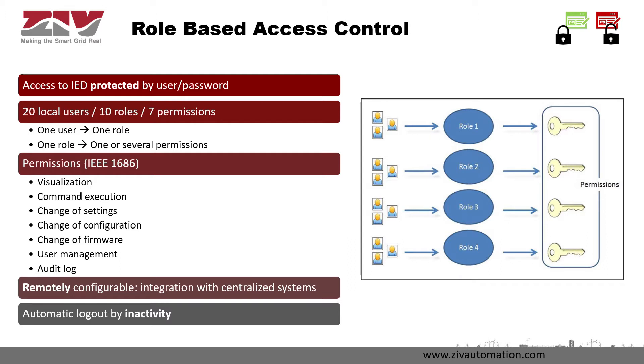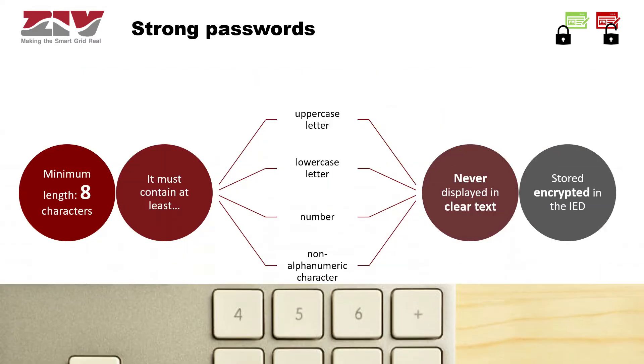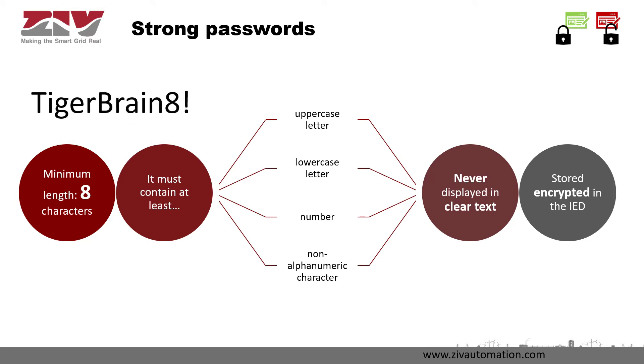The IED also has the functionality of automatically logging out a user by inactivity. The IED implements strong passwords: the minimum length is 8 characters, and it must contain at least one uppercase letter, one lowercase letter, one number, and one non-alphanumeric character. Passwords are never displayed in clear text and are stored encrypted inside the IED.